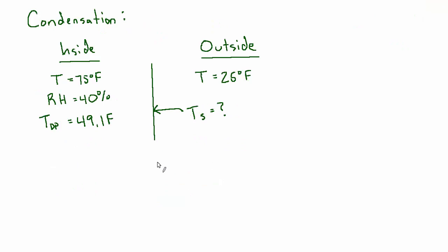Surface temperature is less than inside dew point temperature, therefore yes, condensation will form, and that is answer B. If it was a bit closer then I'd want to drill down more on the properties of this window.